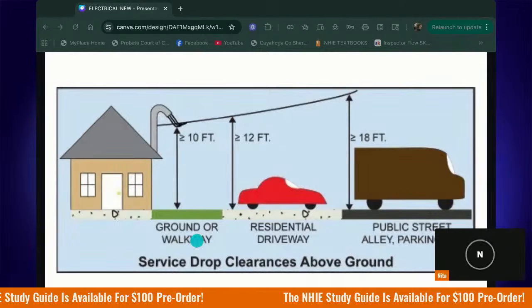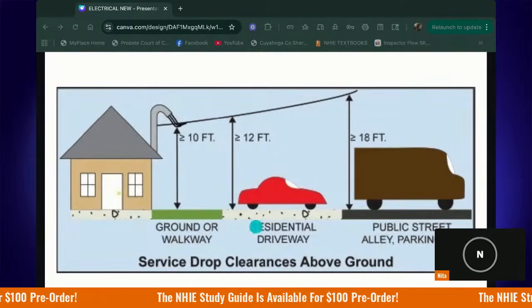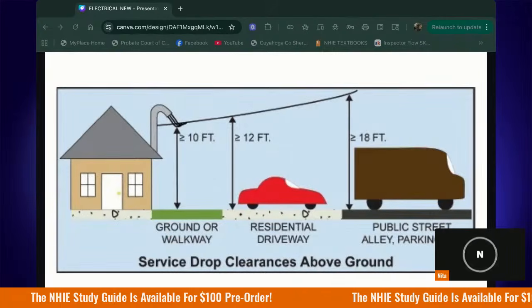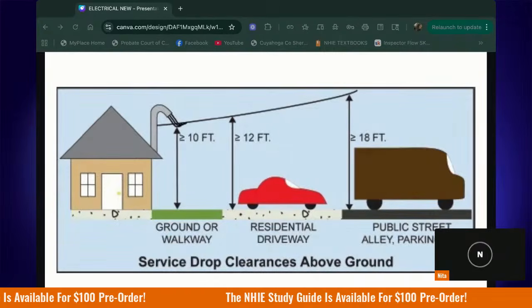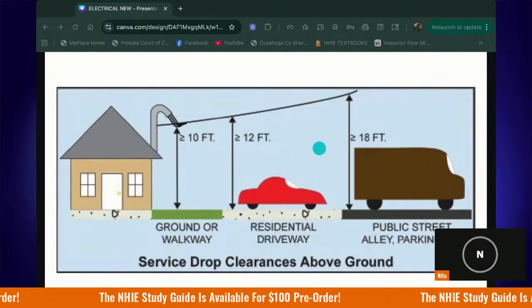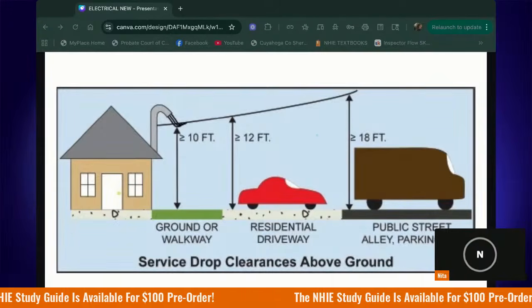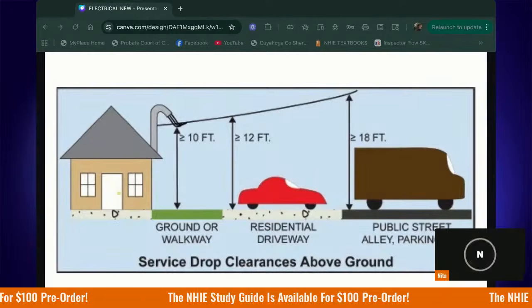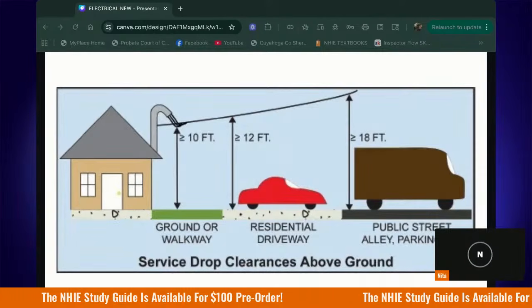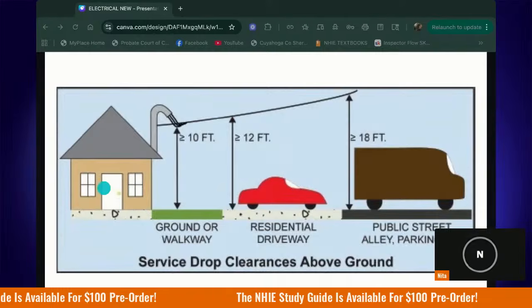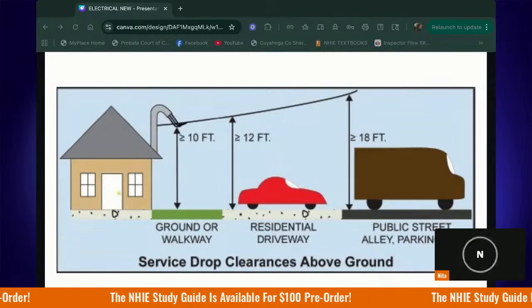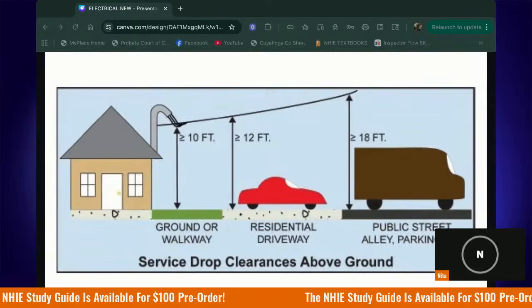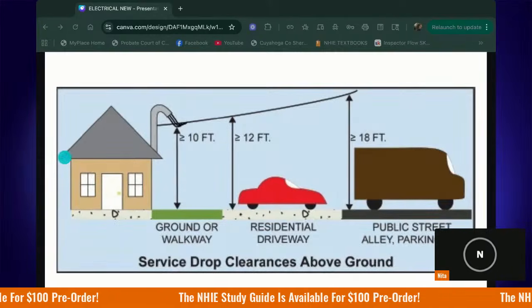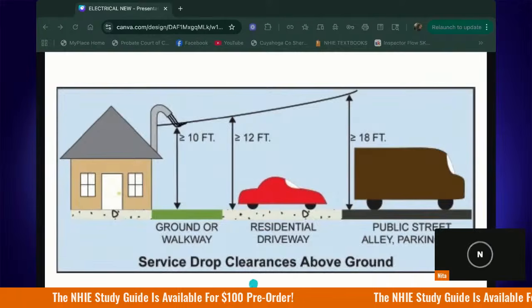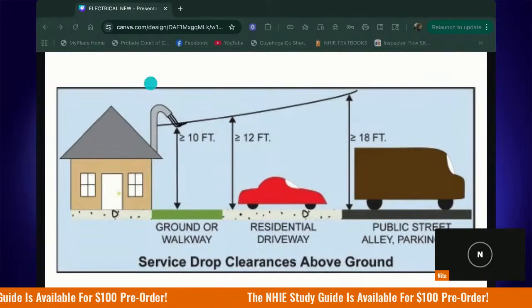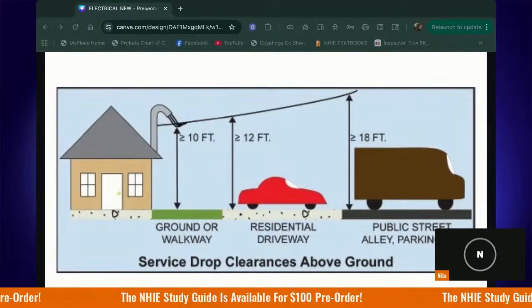So next, our residential driveway, a minimum clearance above the driveway is at least 12 feet. And then the minimum clearance above public streets is 18 feet. So we start closest to the house with 10. Think sidewalk, walkway. The further that we get away, the driveway is 12 feet, and then a public street is 18. Any questions on the clearance requirements?